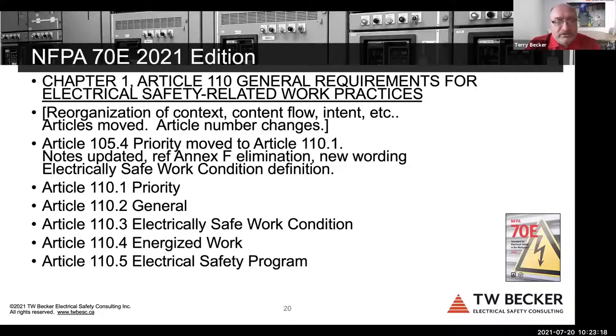Again, this is where the key changes occurred, is the changes bringing forward content from Article 120 and Article 130 and putting it into Article 110. And if you really understand what these standards are doing, and I hope that if you're continuing to use 70E, you'll look at this and go, this makes a lot more sense now, that this is methodically what should happen with the user using this document, right? That we've got the priority to eliminate exposure, some general requirements, and an elimination, establish an electrically safe work condition. Not the detailed procedure, that's still in Article 120, but it's basically saying priorities to eliminate exposure. If you establish an electrically safe work condition, if you can't establish an electrically safe work condition, we need energized work to be justified, and then it gets into the electrical safety program requirement, right?